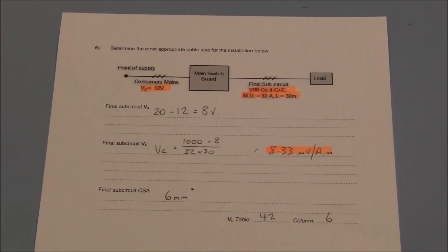Using a 6 millimetre squared cable on a 32 amp circuit may sound excessive from a current carrying capacity. But delivering 32 amps a distance of 30 metres is a substantial undertaking. And this is why voltage drop considerations are necessary.